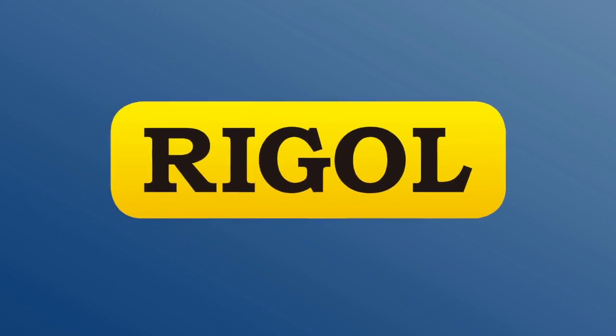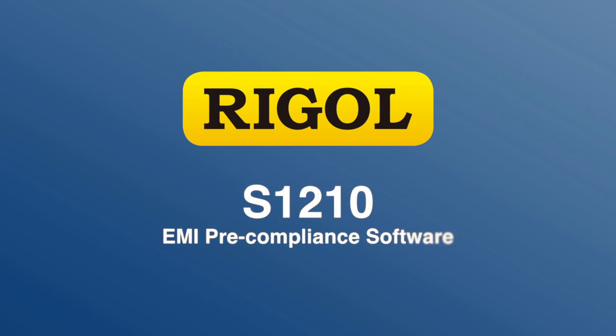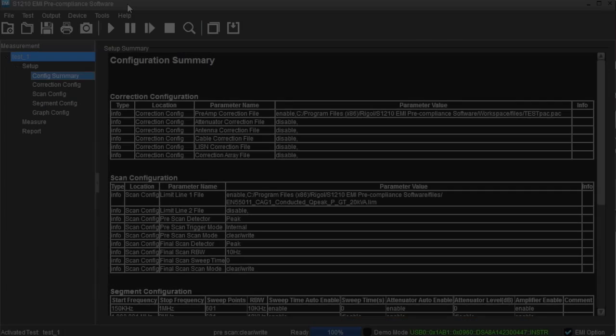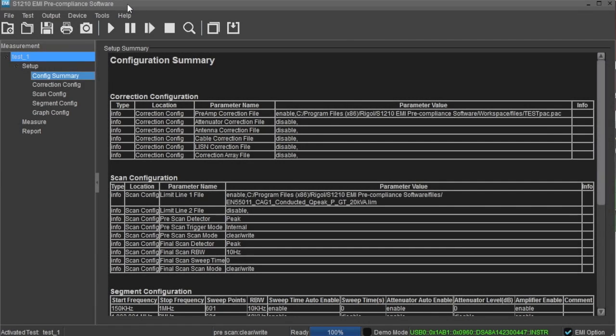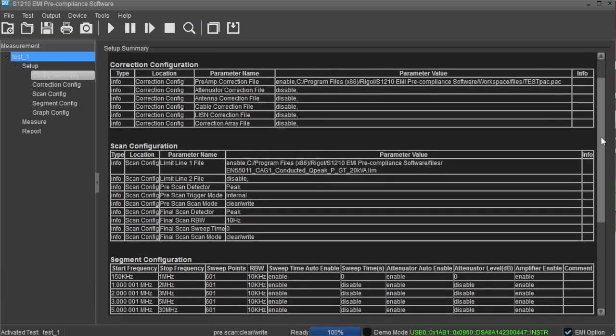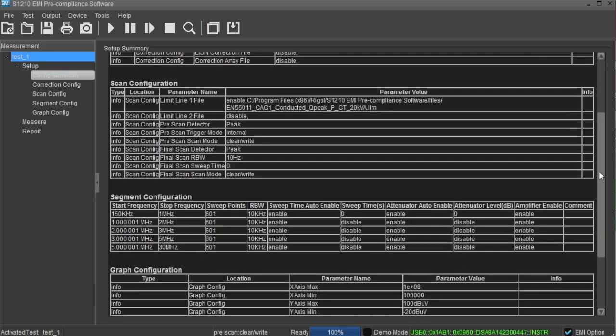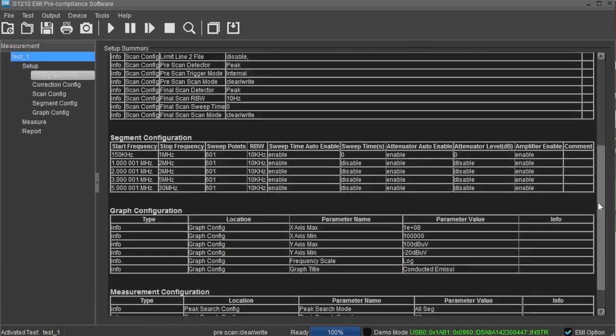The Rigol S1210 EMI pre-compliance software is a PC application developed to ease conducted and radiated pre-compliance measurements when used in conjunction with the Rigol DSA series spectrum analyzer. The software contains all of the associated drivers to connect remotely to your instrument. On the left side of the window, there are a number of labels that help to configure the scan and also monitor the performance of your system. The configuration summary shows all of the instrument settings, environmental, and other setup parameters that may be important to your final pre-compliance report.